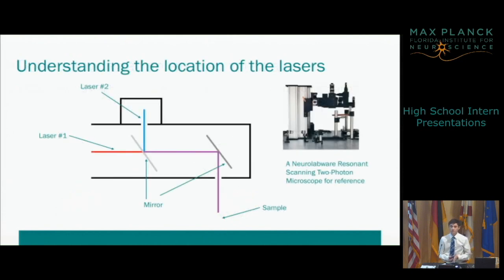But before I can make the part, I have to understand the location of the 2 lasers in this microscope. Laser number 1, which activates the neurons, is located in the base of the microscope and is in a fixed position. For it to reach the sample here, it has to go through the mirror, this first mirror found here. Laser number 2, located on the top of the microscope, is also in a fixed position and bounces off the same mirror that laser 1 goes through, and then they become one singular laser. This laser then is used to record the measurements and information needed for the scientists.